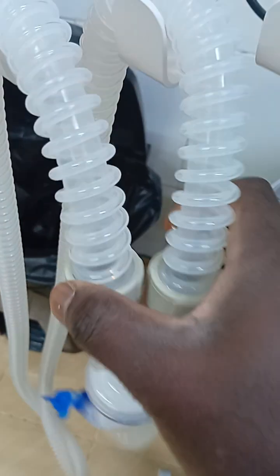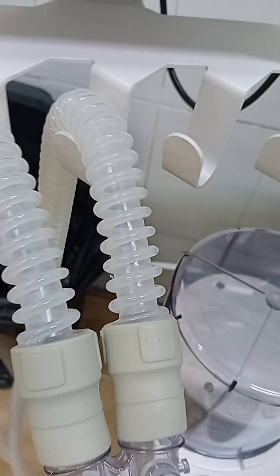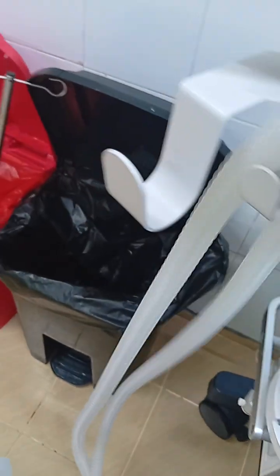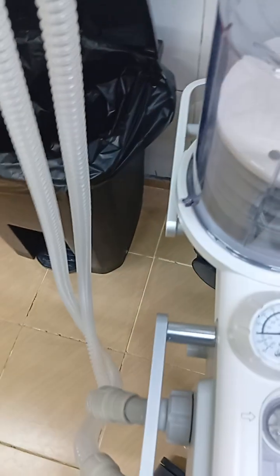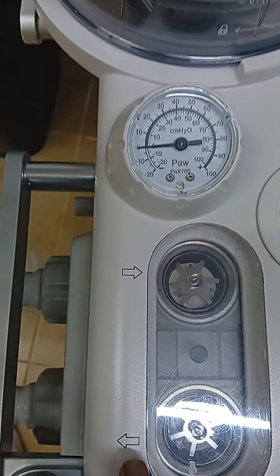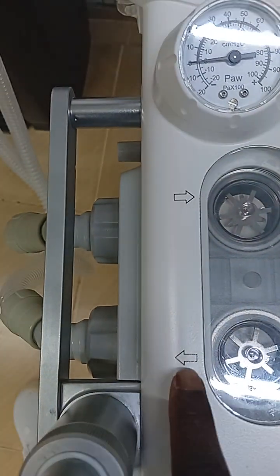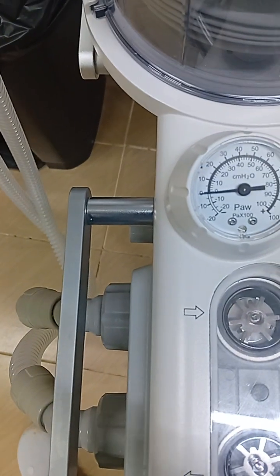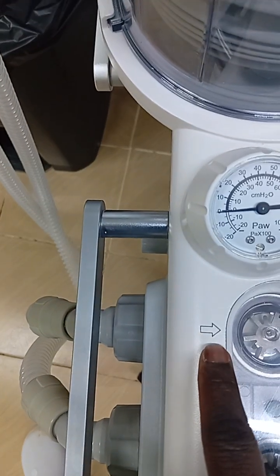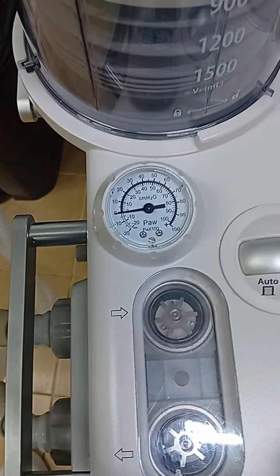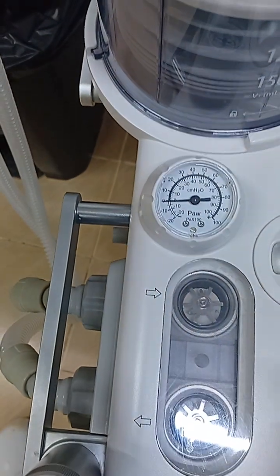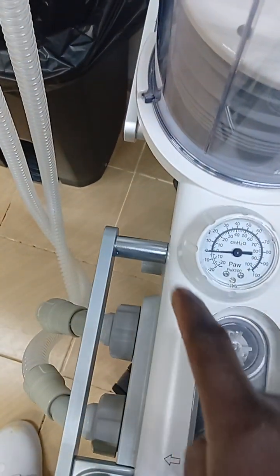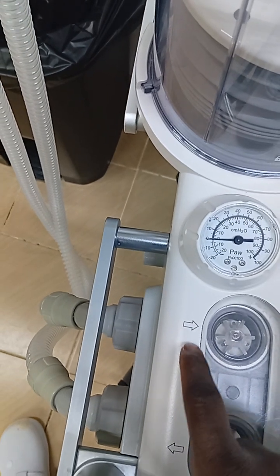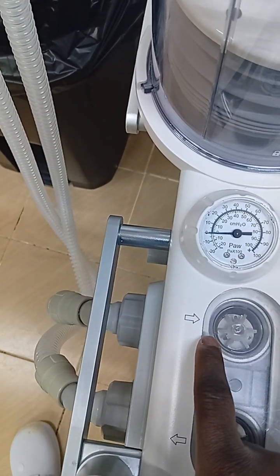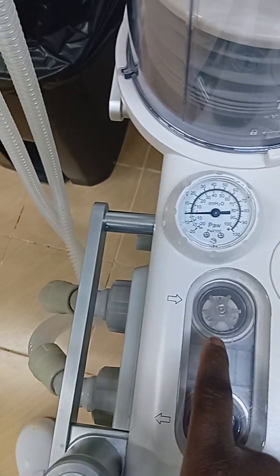Of course, here beside the bellows we have the breathing tubes. We have two breathing tubes. As you can see from the arrows, one is for inspiration and the other one is for expiration. This one is the expiration tube. So one tube will be taking the air and the anesthesia gases to the patient, and the expiration tube will be taking the gases out of the patient, the gases that the patient is exhaling, and it will be going back to the machine.